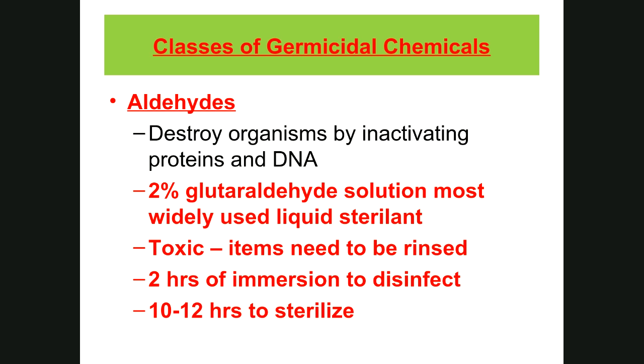Next group are very strong chemicals. These are the aldehydes. They are glutaraldehyde, formaldehyde. Nowadays, what we use is glutaraldehyde. 2% solution of glutaraldehyde is typically what is used. It is a sterilant, but you do need to submerge in the glutaraldehyde for a long time, for 10 to 12 hours to sterilize. 2 hours is enough for disinfection. Downside, it is toxic. So whatever is immersed into this solution will have to be rinsed.